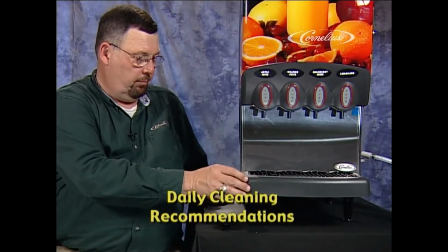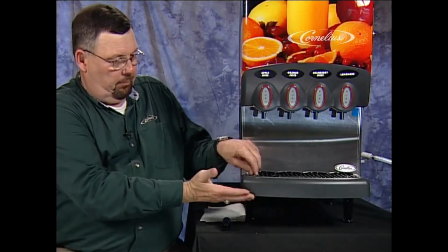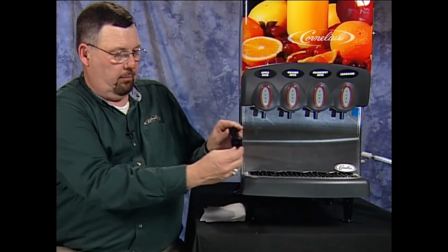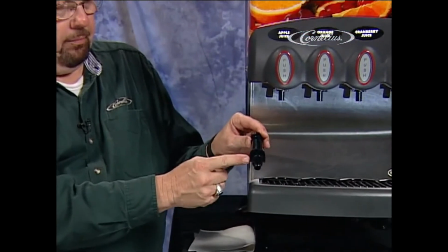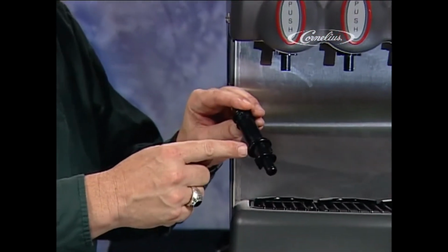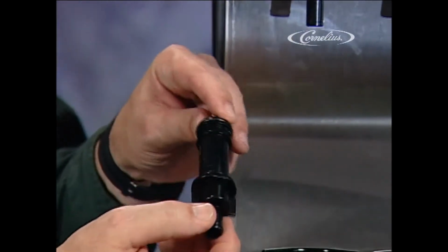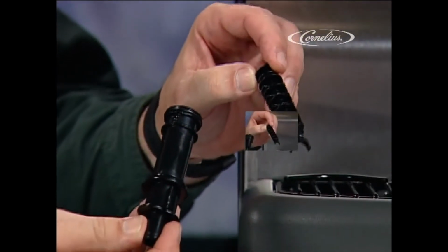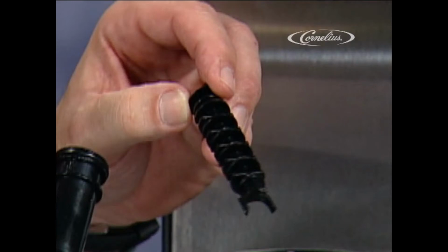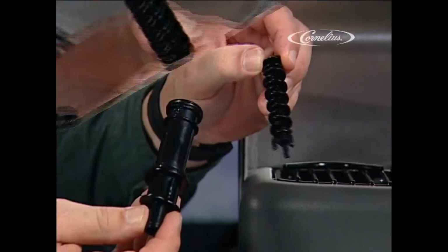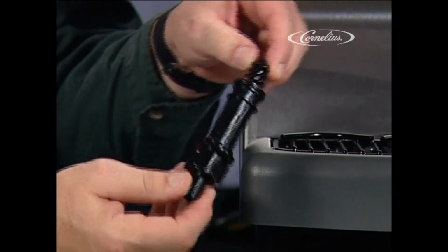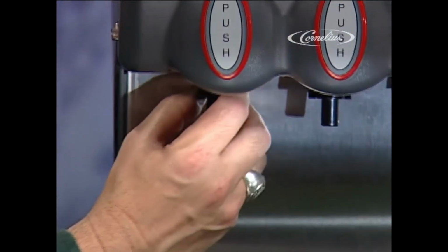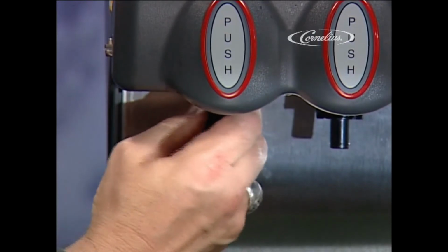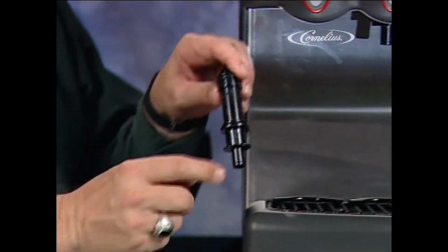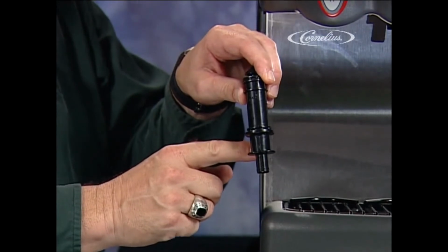We strongly recommend daily cleaning of the following parts using a mild dish detergent: cup rest, drip tray, dispense nozzles, and mixers. The dispense nozzles are held by protruding little wings on opposite sides of the nozzle opening. We reference these wings when we're installing and deinstalling the nozzles. The static mixers are inserted to the top of the dispense nozzles and look very much like a giant screw. To remove the dispense nozzles and static mixers, rotate each 90 degrees and pull it down from the dispense compartment. Imagine the numbers on a clock. Put the nozzle wings in the 6 and 12 position, or north and south, and pull straight down to release.